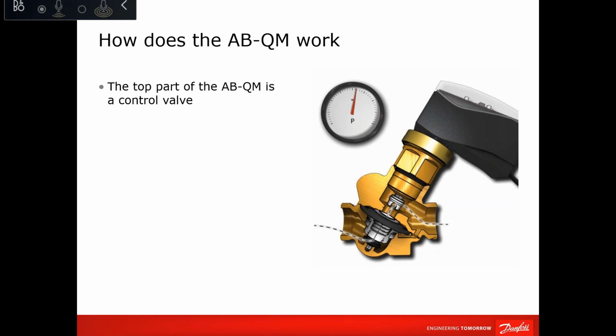But yes, we already did a lot of projects with flow measurement using the KV methodology on all sizes. In some projects I saw 5% accuracy, which is perfect. Other projects I saw 10, which is still okay. Some I saw 15, but 15 and 12% was only on a few valves near the pump, because they did not optimize the pump yet. But in some of the projects where we did the commissioning, we were able to achieve from -5 to +10 as an accuracy, which is perfect and approved by every test and commissioning party. Yes, we can measure the flow. That is to answer the question. Yes, flow can be measured like any DRV.